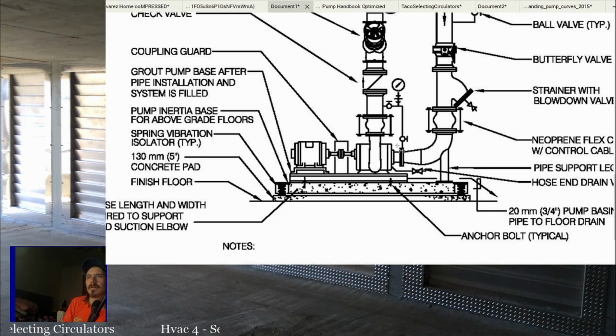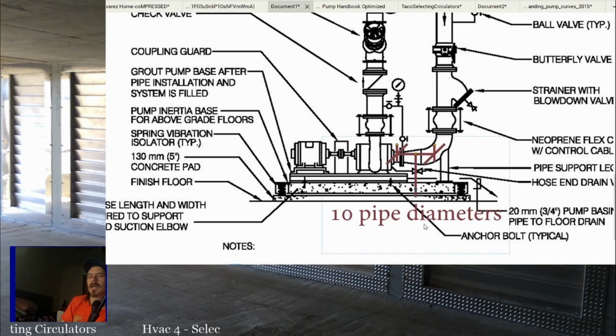The dimension from here to here, all right, should be 10 pipe diameters. So if this is 3-inch pipe on the suction side, you should have 30 inches between a 90 and the pump. Okay. Even on inline pumps, having good straight pipe before the pump is important. So you need at least 10 pipe diameters before the inlet of a pump. And that's going to make sure that you have a much smaller possibility of cavitating.